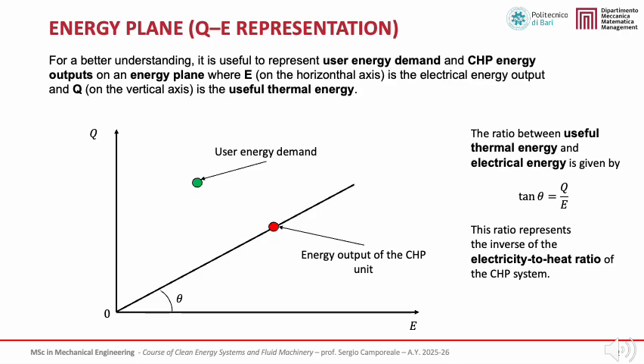The straight line passing through the origin represents the characteristic of the CHP system, showing the coupling between electricity and useful heat production. The angle theta defines the ratio between thermal and electrical energy, with its tangent equal to Q over E. This quantity represents the inverse of the electricity to heat ratio of the CHP system. By comparing the position of the user demand with the CHP operating characteristic, this representation allows us to visually assess load matching, operating strategy, and the suitability of heat-led or power-led operation.